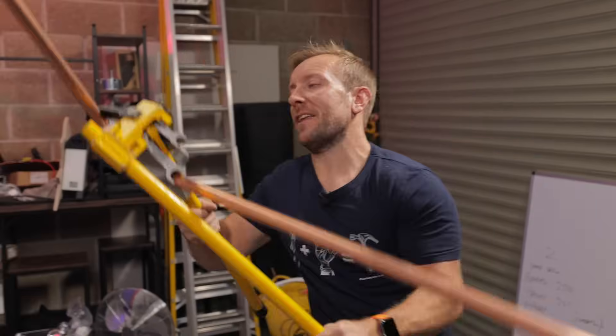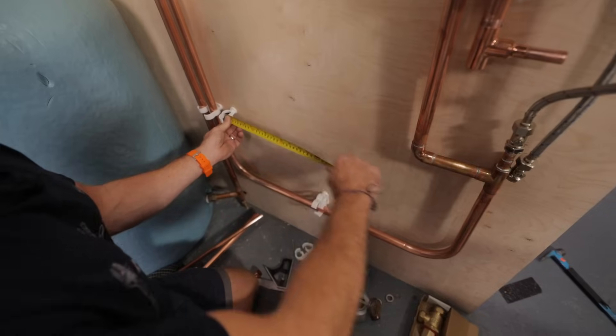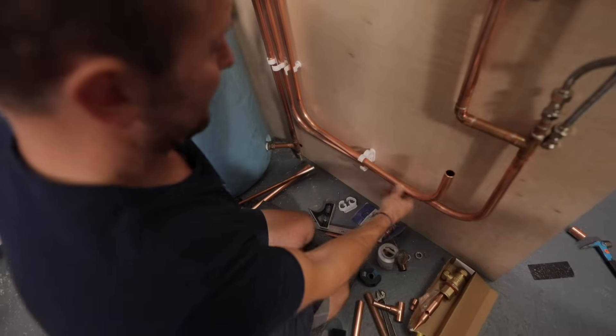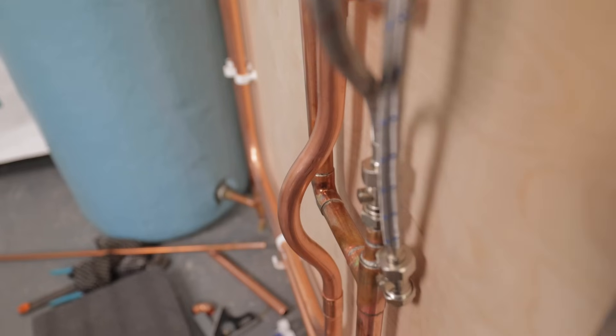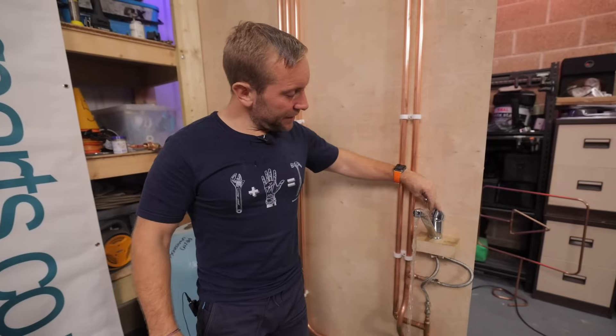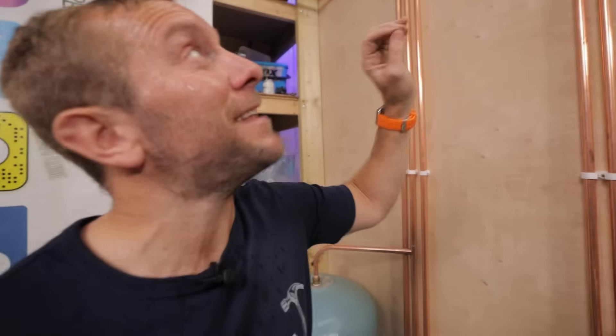So now we've got our vented unpumped system installed. Before we look at the pump, let's check the current performance before we install it — this should demonstrate the lack of flow and pressure that you've probably got in your own home, and the reason you're currently watching a video on how to solve this problem. Everything's back on now. This is the cold pressure down the bottom — not great. This is the hot pressure. And this is the mixed output. Got a little bit of water coming out up there at the bathroom tap. That's a demonstration of the problem we've got in this system.